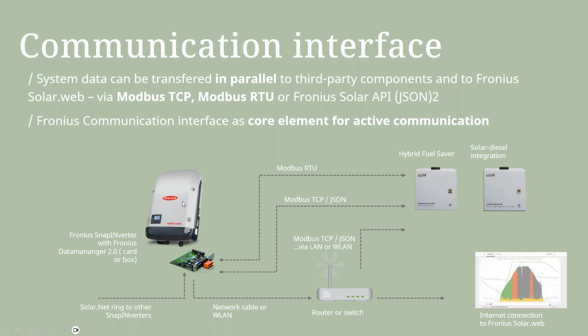The same thing also applies to all Fronius Snap inverters, but it is important to ensure that we have at least 1 data manager in the cluster or in the SolarNet ring. So please ensure that the optimal number of Snap inverters are connected per SolarNet ring. For most third-party devices, it is recommended to have 6 Snap inverters per SolarNet ring. Okay, so this is to ensure the fastest communication and reaction time for the PV-Genset setup. Good.